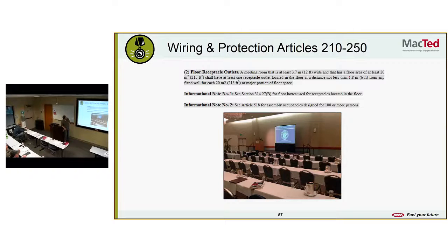If a meeting room is at least 12 feet wide and has a floor area of at least 215 square feet, it shall have at least one receptacle outlet located in the floor, at a distance of not less than 6 feet from any fixed wall, for each 215 square feet or major portion of the floor space. Okay. Any questions on the meeting room receptacle requirements? Good to go?